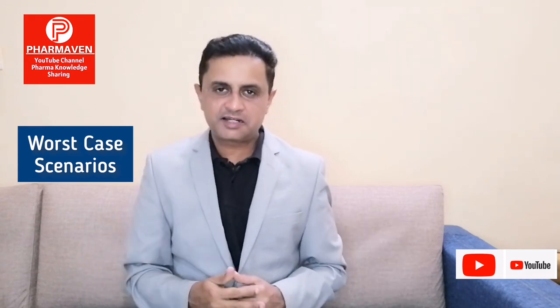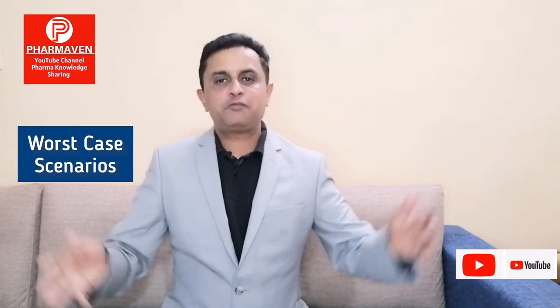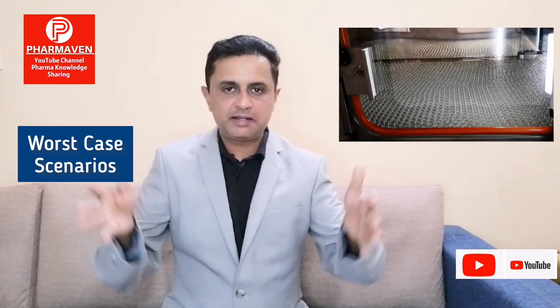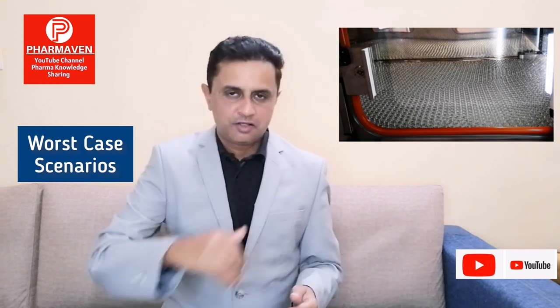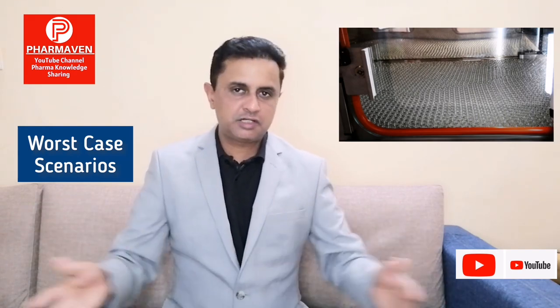Now what is the second worst case? When my entire tunnel, my entire hot zone, is filled with vials, then the entire mass is to be heated by the air. So the middle of the mass will be my second worst case scenario, because it is fully loaded and surrounded by all the vials. Now the entire tunnel is filled and the entire glass load has to be heated to achieve the depyrogenation temperature.